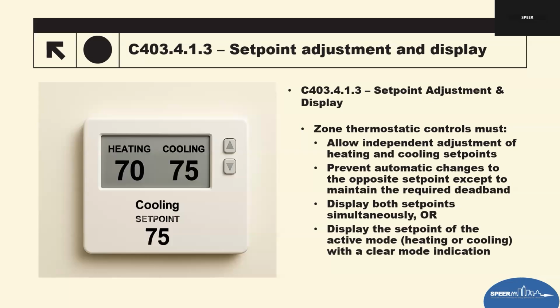We just kind of went through that. But an example basically is what we just said. If someone raises the set point for cooling, basically that it will violate that deadband if they're moving heating at the same time. And then display requirements. There is a display requirement in there. So the code also addresses how set points must be displayed, which is especially important in BAS interfaces and touchscreen thermostats, like what we see kind of here.